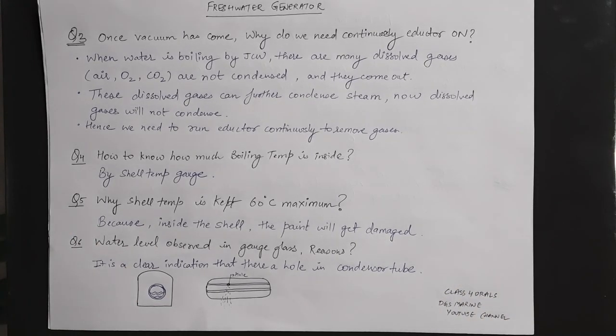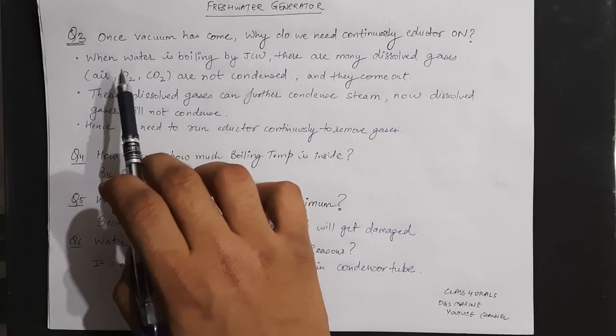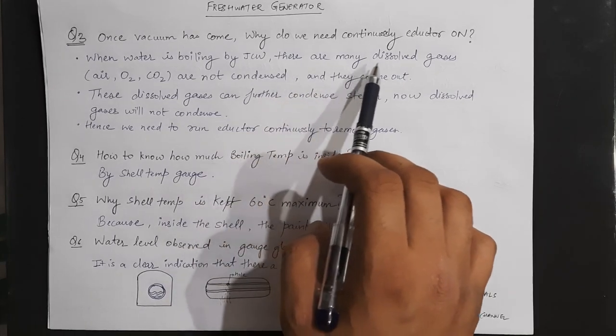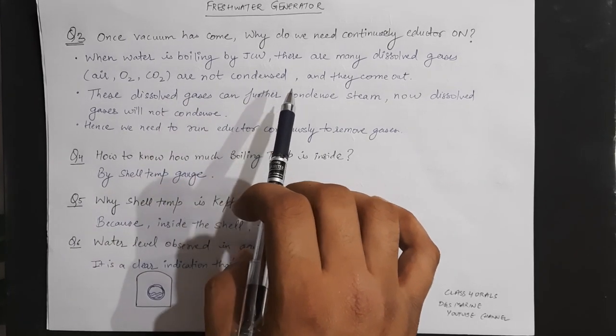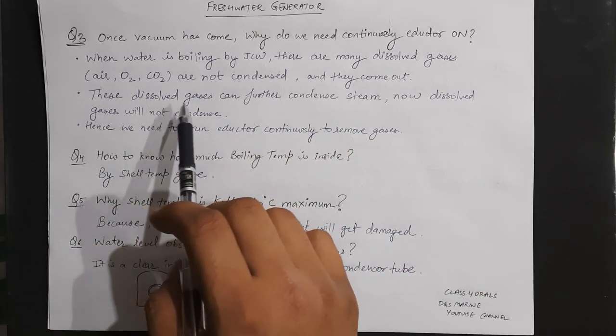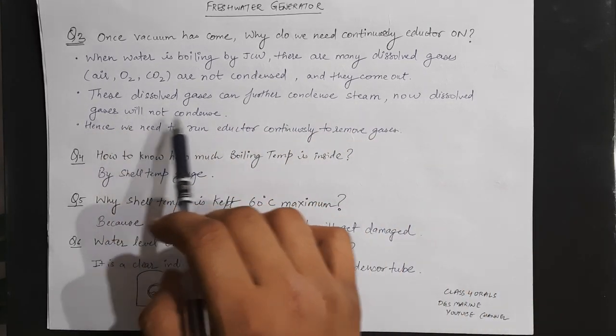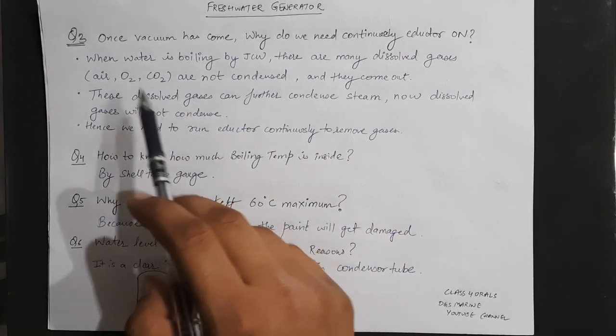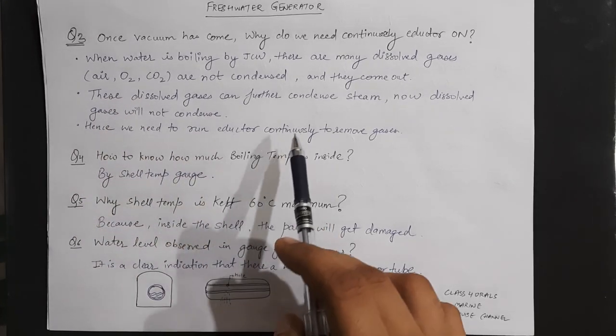The third question is: once the vacuum has come, why do we need to continuously keep the ejector on? When the water is boiling by the jacket cooling water, there are many dissolved gases — air, oxygen, CO2, etc. — which are not condensed and they come out. These dissolved gases will not condense and can hinder further steam condensation. Therefore, to keep on removing these dissolved gases, we need to continuously run the ejector to remove them.